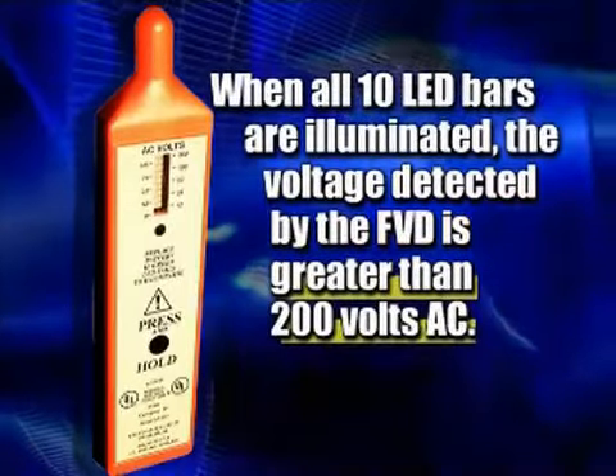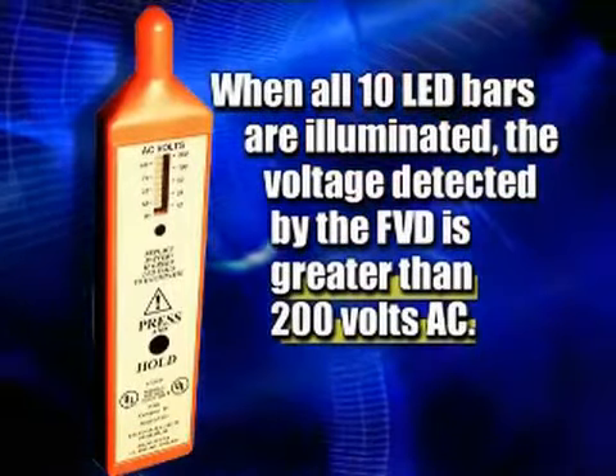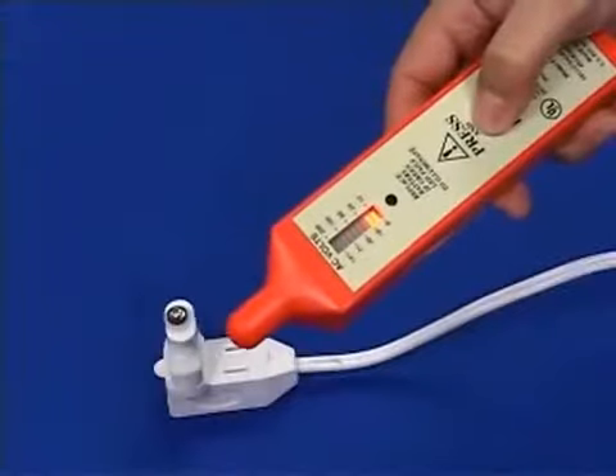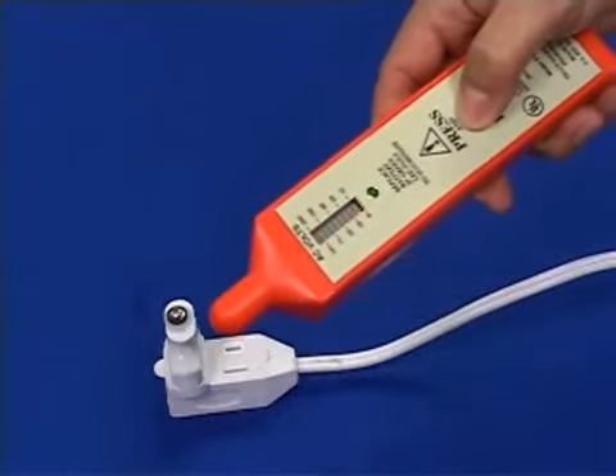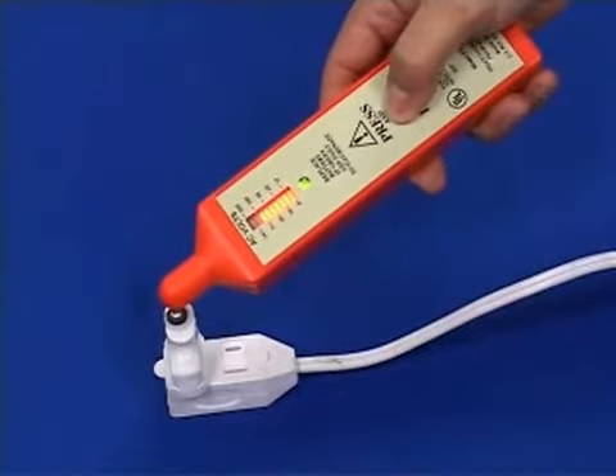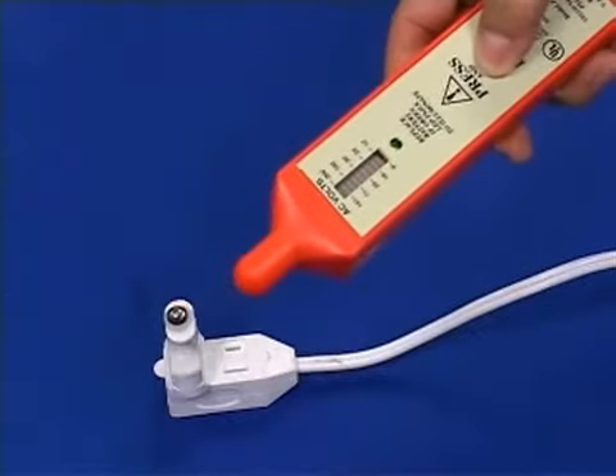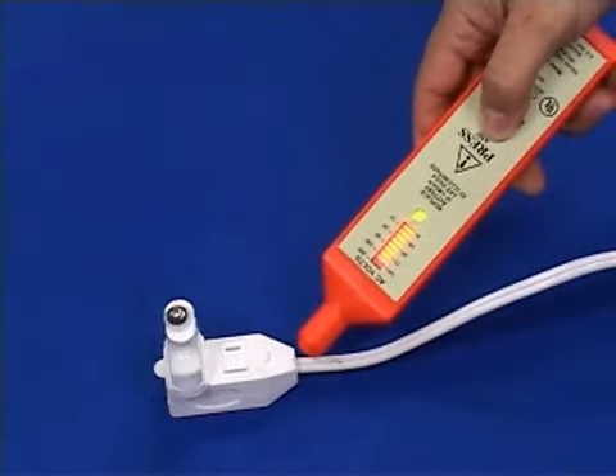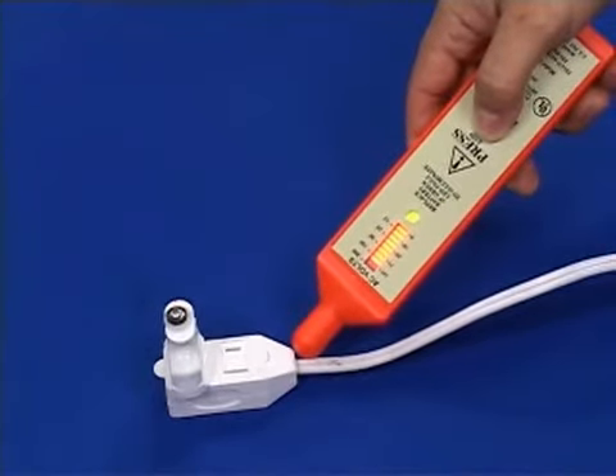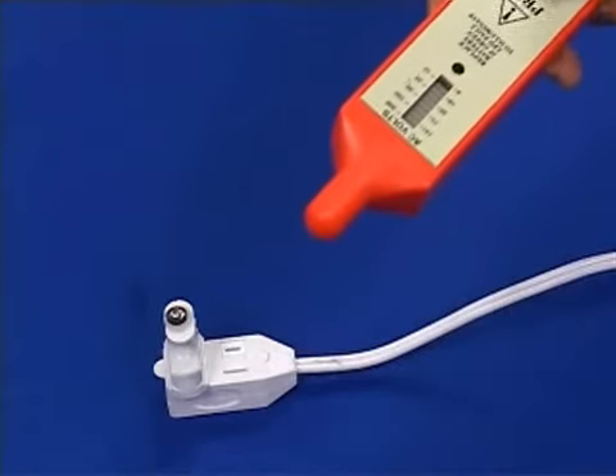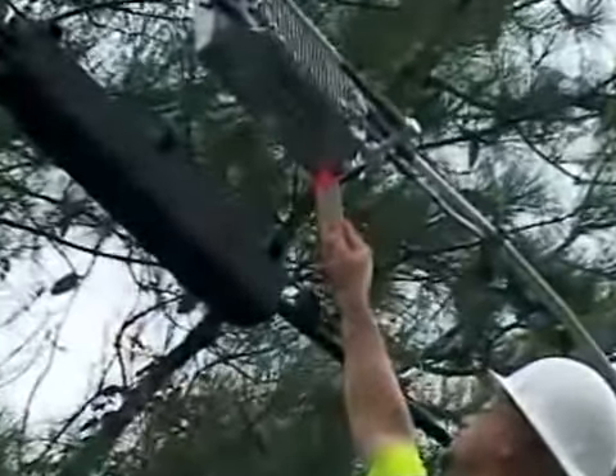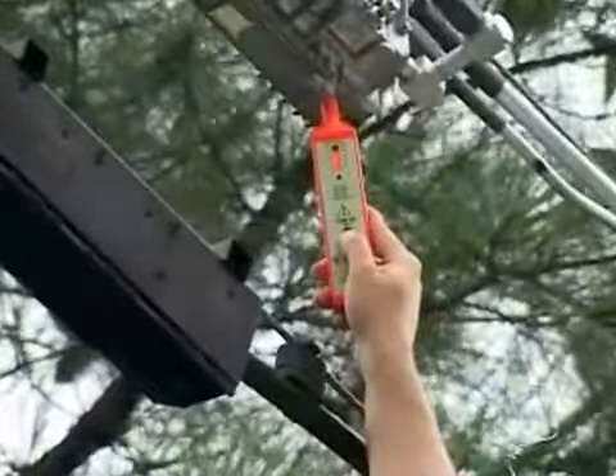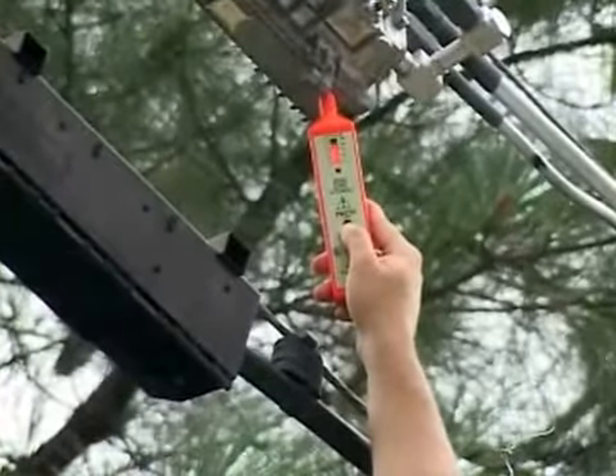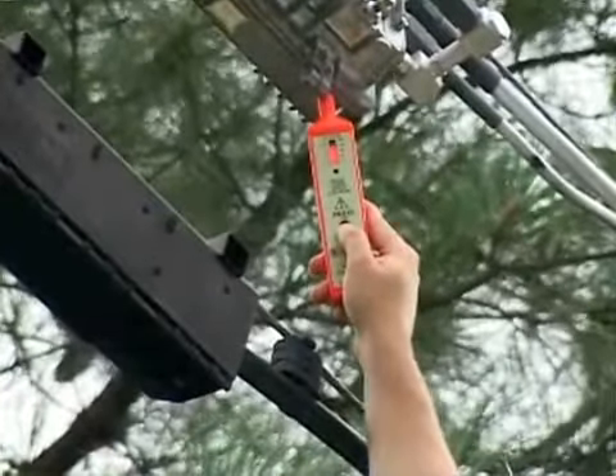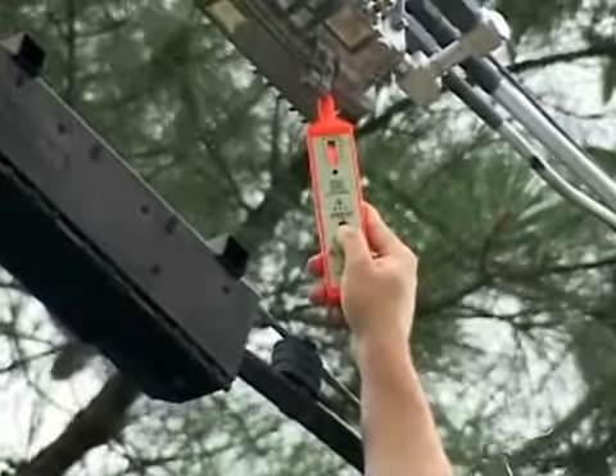When all 10 bars are illuminated, the voltage detected by the FVD is greater than 200 volts AC. The FVD is calibrated with the probe in contact with an insulated 22-gauge pair that is energized. When the 6th step of the bar graph is activated, 50 volts of AC have been detected. Along with the 6th bar graph step, another indicator, an audible alarm, will also be activated. The audible alarm will remain active as long as more than 50 volts AC are detected.